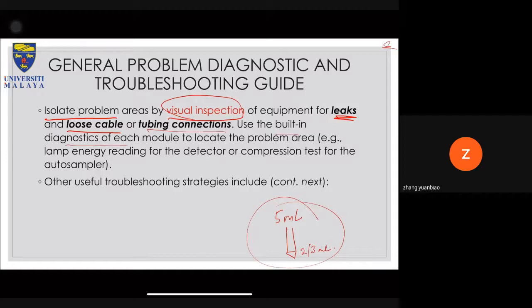Use the built-in diagnostic in each module to locate the problem area. Example, lamp energy reading of the detector, or compression test for the autosampler. So this is more on the software side, so depending on the software, you might be able to run this. I know we do have some software for Agilent and Shimadzu that can tell you if there's any issue being detected throughout the system. But you might sometimes work with an old system that does not have this kind of feature, so you still need to do a visual inspection.